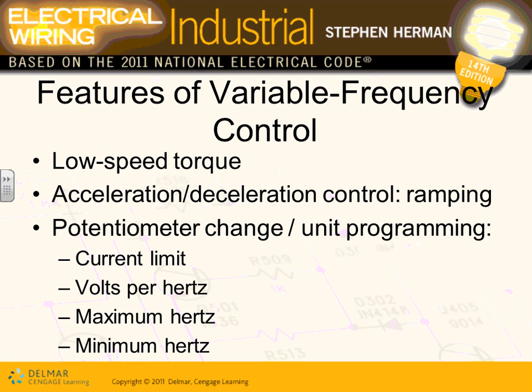I can ramp my motor up. When I shut it down, I can ramp it down. And when it's running at full speed, guys, I can also control the speed. Running at 500 RPM, 1800 RPM, 200 RPM. You know what I mean? So isn't that cool? If you have a conveyor and you can control the speed now, instead of things being all over, you can run it as slow or as fast as you want. Big deal in the machine and manufacturing industry, guys. Big revolution.